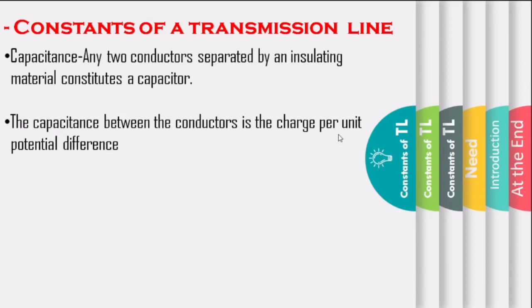Coming to capacitance: any two conductors separated by an insulating material constitute a capacitor. As any two conductors of an overhead transmission line are separated by air, which acts as insulation, capacitance exists between any two overhead line conductors. The capacitance between the conductors is the charge per unit potential difference, that is, capacitance C is equal to Q by V farads, where Q is the charge on the line in coulombs and V is the potential difference between the conductors in volts. The capacitance is uniformly distributed along the whole length of the line and may be regarded as a uniform series of capacitance connected between the conductors.